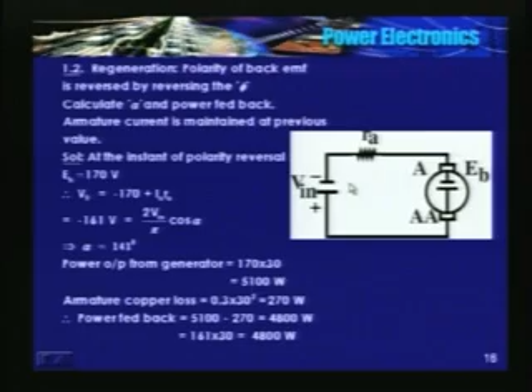What is the power fed back to the source? It is nothing but V in into I average, or output power of the generator minus IA squared into RA. What is the power output of the generator? EB into IA, 170 into 30 is the output power of the generator, minus I square R losses, 270 watts. Therefore power fed back is power output of the generator minus I square R losses. This should also be equal to V1 into I1 into cos of the angle between V1 and I1.